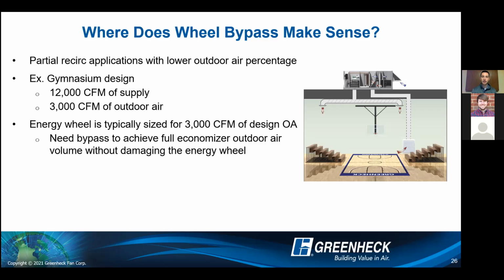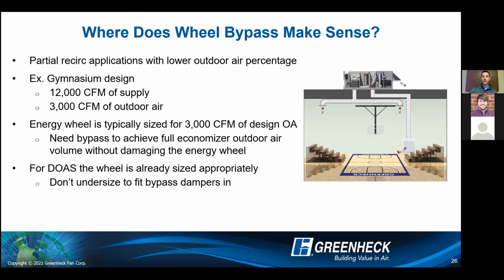But when we go into economizer, we're ramping up that outdoor air damper and bringing in more outdoor air, potentially up to 12,000 CFM. Well, the energy wheel is only sized for 3,000. So if we put 12,000 CFM through that energy wheel, there's a good chance that that wheel is going to blow apart. So we don't want to damage that energy wheel. So that is where wheel bypass makes sense, right? We put the energy wheel bypass in there.